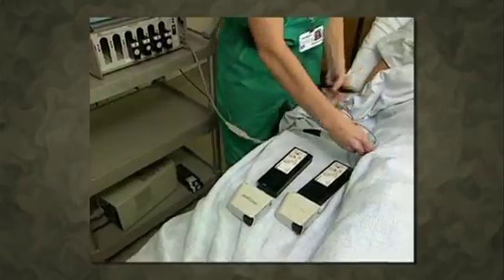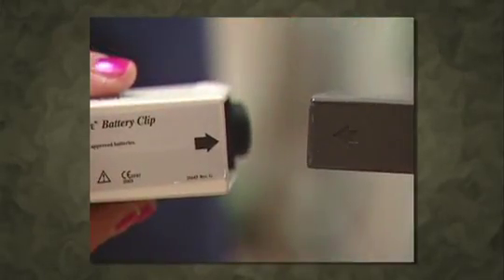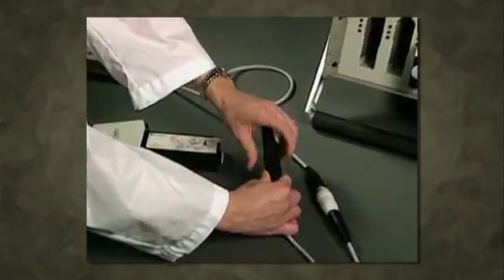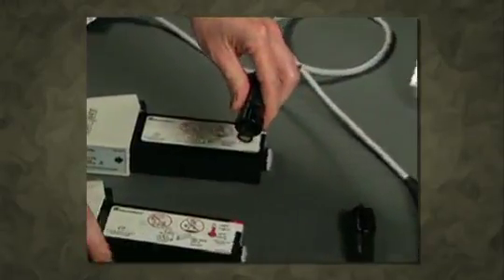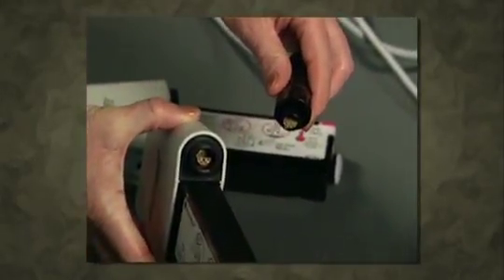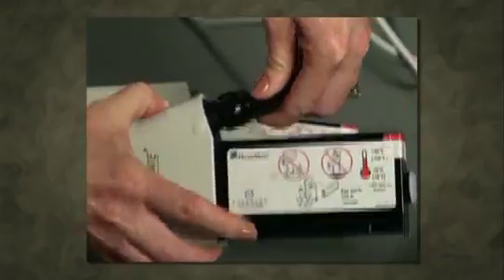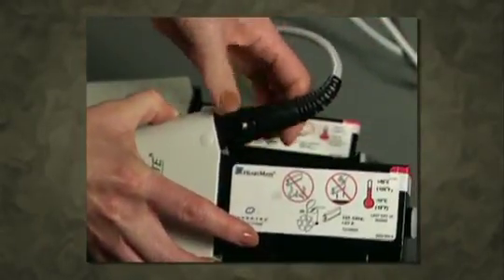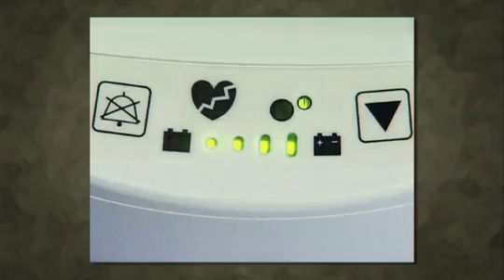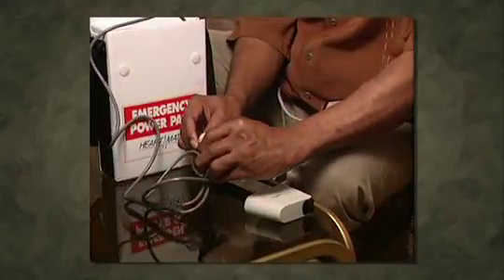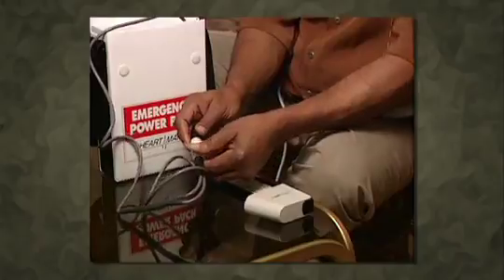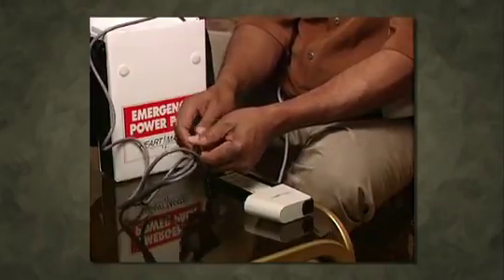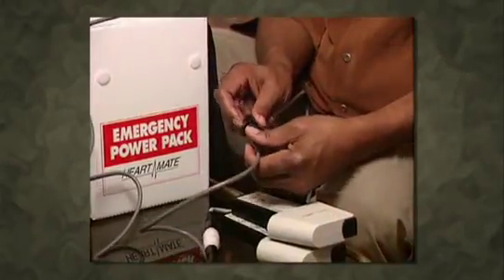While the system controller is designed to be connected at all times with two cables to the power module or to two batteries, the pump runs effectively on just one. This allows for changing batteries or switching from batteries to the power module to occur without any impact in flow or patient condition. Therefore, even when a mechanical problem occurs, it may not result in an immediately life-threatening situation, but rather one that just requires the patient to make plans to get to their hospital to have the situation evaluated.